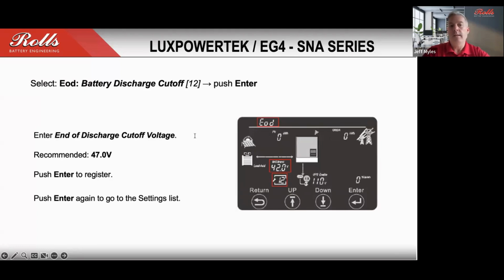And again, some other settings, for those of you that have worked with lead acid, whether it's flooded or AGM, oftentimes you would have a discharge cutoff voltage. You're still going to program that. Now, the BMS will actually shut the system down based on low voltage, but we recommend setting that at 47. That's just to ensure that it's triggering that before the BMS has to do that.